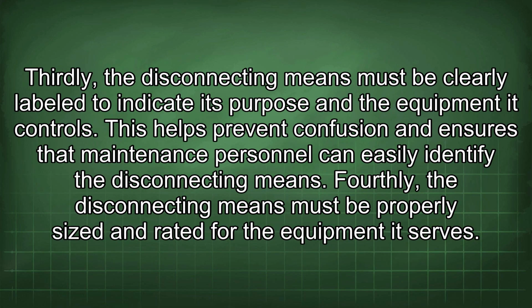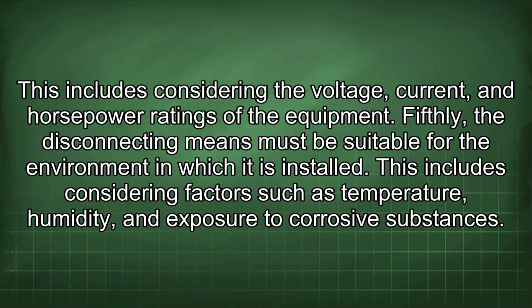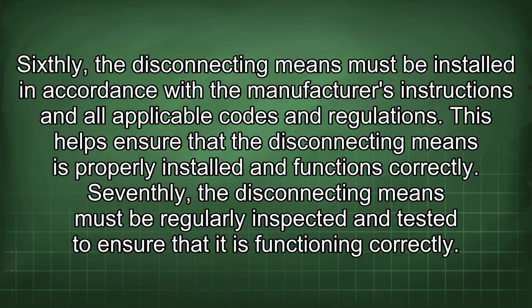Thirdly, the disconnecting means must be clearly labeled to indicate its purpose and the equipment it controls. This helps prevent confusion and ensures that maintenance personnel can easily identify the disconnecting means. Fourthly, the disconnecting means must be properly sized and rated for the equipment it serves. This includes considering the voltage, current, and horsepower ratings of the equipment. Fifthly, the disconnecting means must be suitable for the environment in which it is installed. This includes considering factors such as temperature, humidity, and exposure to corrosive substances. Sixthly, the disconnecting means must be installed in accordance with the manufacturer's instructions and all applicable codes and regulations. This helps ensure that the disconnecting means is properly installed and functions correctly.